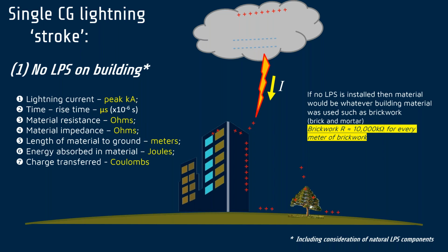And we talk about surge arresters. When you rate a surge arrester, you rate it for the anticipated energy that it has to absorb as it tries to take all the energy from one side to the other, particularly on our MV, medium voltage networks, where the practice of putting a shield wire on to try and guide the lightning away from our power system has a contradicting problem in that the insulation levels are too low for that resistance. You keep coming back to this item that the resistance is a real deal breaker. So with medium voltage networks, if we have a back flashover, back flashovers are typically in the order of nanoseconds, whereas the lightning is in the order of microseconds. Nanoseconds means that di/dt is even faster and causes bigger problems. So we don't want back flashovers and air gap flashovers.